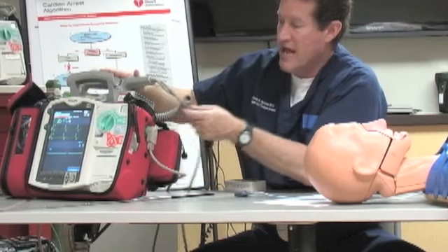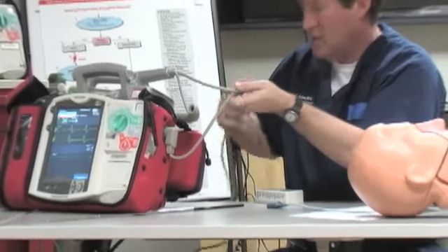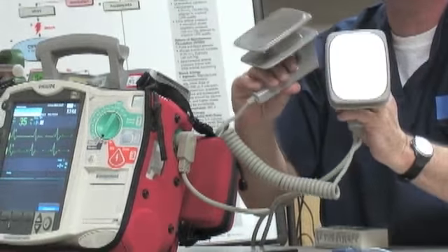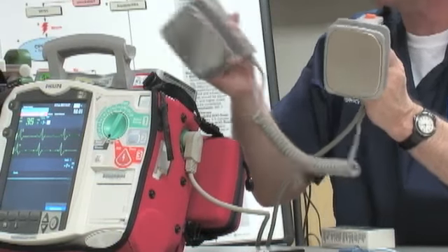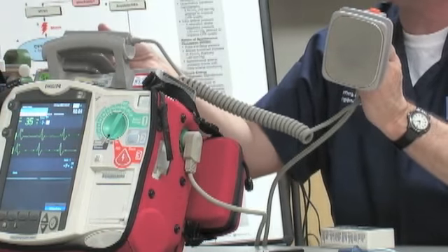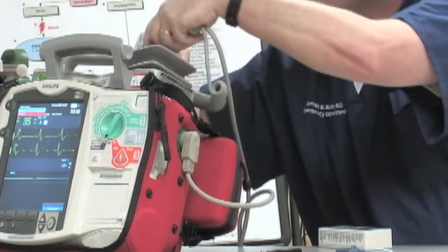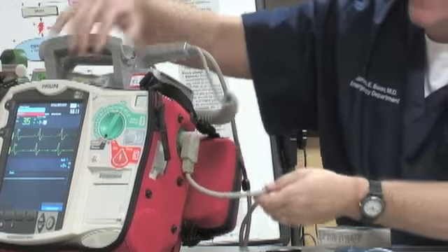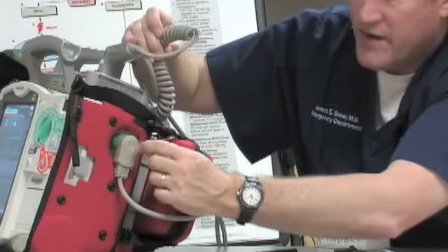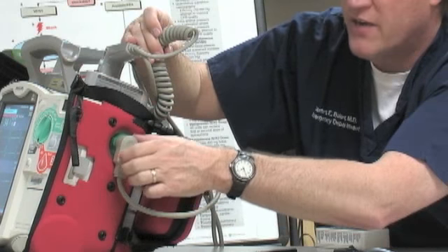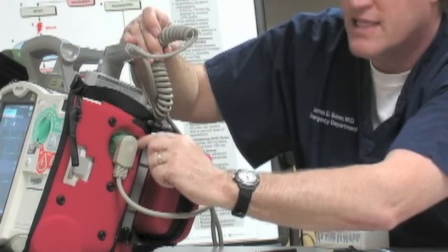and we need to hook this up to our monitor so it works. Many monitors will have the gray cable attached because the gray cable is already hooked up to our manual paddles. American Heart Association guidelines suggest that we don't use these manual paddles if we can help it. It's much safer to use the multifunctional pacing pads. So what I'm showing you here is you see the gray pads attached to the gray cable and the gray input here.